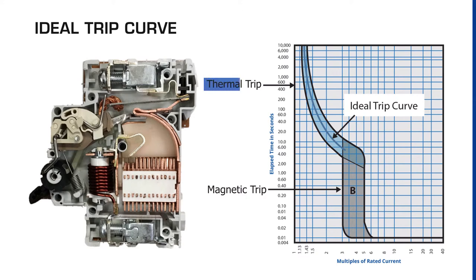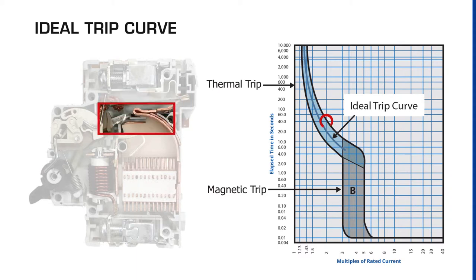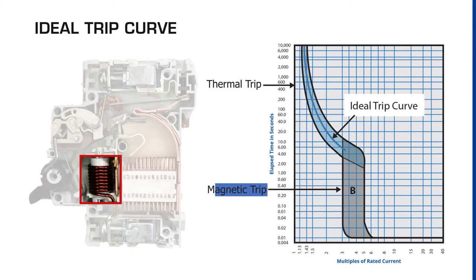The top of the chart shows the thermal trip curve for the bimetallic strip. It tells us that at one and a half times the rated current, the quickest the circuit breaker will trip is forty seconds, and forty seconds at two times the rated current is the slowest the circuit breaker will trip. The bottom of the chart is for the magnetic trip of the coil or solenoid. At 0.02 to 2.5 seconds at three times the rated current, that's the soonest the circuit breaker is going to trip. The same duration, 0.02 to 2.5 seconds, at five times the rated current is the longest it will take the circuit breaker to trip.